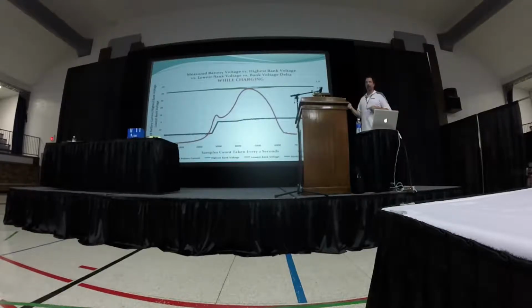That's one thing I noticed, and we've never really done that kind of comparison before. We've looked at high cell, low cell, but in banks of 12 cells like this, even under heavy loads, that voltage delta is really, really small. 2 to 20 millivolts, maybe 30 millivolts, even at 1,000 amps.